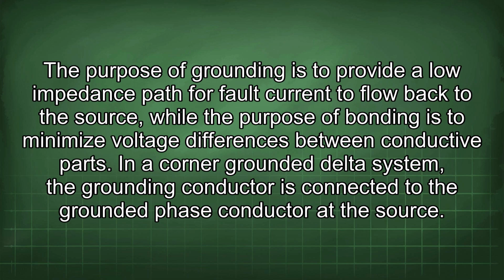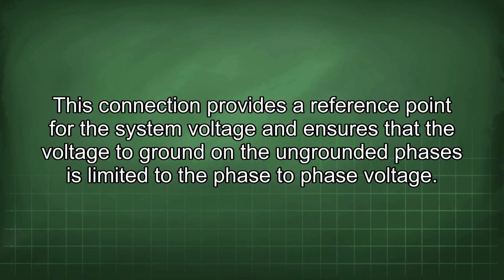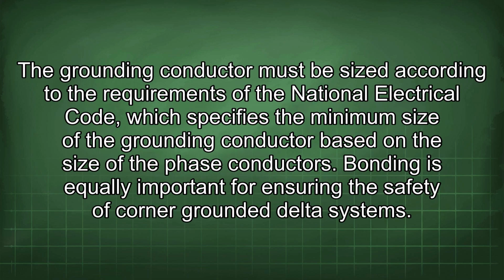In a corner-grounded delta system, the grounding conductor is connected to the grounded phase conductor at the source. This connection provides a reference point for the system voltage and ensures that the voltage to ground on the ungrounded phases is limited to the phase-to-phase voltage. The grounding conductor must be sized according to the requirements of the National Electrical Code, which specifies the minimum size of the grounding conductor based on the size of the phase conductors.